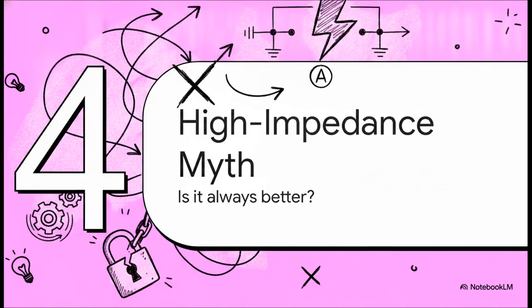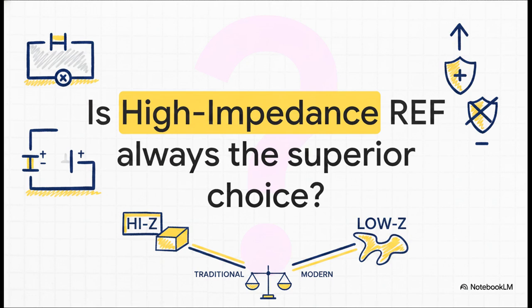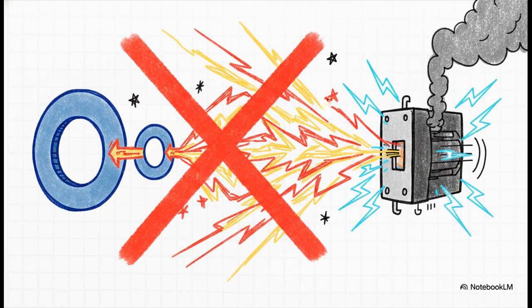Okay, Section 4, the high impedance myth. We've got to clear up a misconception that causes so many commissioning delays. A lot of engineers assume that because high impedance REF is the traditional ultra-stable method, it's just automatically the superior choice every time. So, true or false? Is high impedance always the way to go for the best protection? That is a hard false. If you're working on a retrofit with legacy CTs of unknown or mismatched ratios, low impedance isn't some second-rate compromise. It's literally the only workable option.